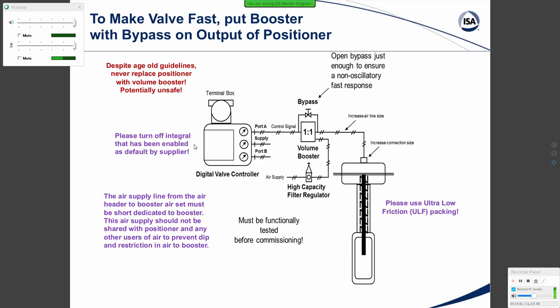We really need to turn off integral action in the positioner and realize the implication of closed-loop control. Once you do that, you can actually use a higher positioner gain, because when you use integral action in PID control, you have to back off on the proportional action accordingly. You should be relying more on proportional and maybe derivative control in the positioner. Unfortunately, it seems like multiple manufacturers are copying each other, and several if not all throttling valve manufacturers have mistakenly turned on integral action in their smart positioners — which means they're really not that smart.